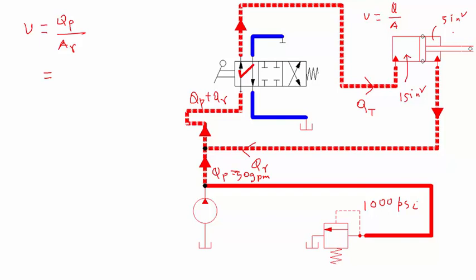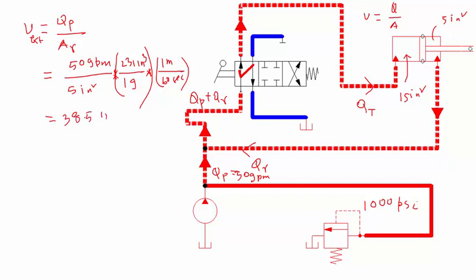Then if we want to calculate the extension velocity, it's going to be QP 50 gallons per minute by the rod end area, which is 5 inches square. Now the gallon per minute I can cancel by the gallon, cancel that, divide by gallon. 231 inch cube is 1 gallon. I can cancel that inch as well. Now let's cancel the per minute, so I want to cancel the per minute, so I will multiply by minute, and that is equal to 60 seconds. So here I have not changed any number. However, I changed the unit.